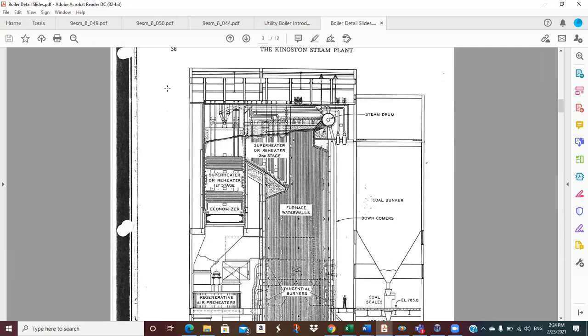Kind of interesting. So all of this is structural stuff, suspended from the ceiling so it can grow as it gets hot, or shrink if they take it offline. And of course that growing and shrinking induces stress in all those components. So the more this thing is put on and taken off, the more you change load from high load to low load, that changes temperature and induces stress in a lot of different system components. So the more you cycle a coal plant up and down, the more rapidly you are damaging the equipment just from the thermal cyclic stresses.